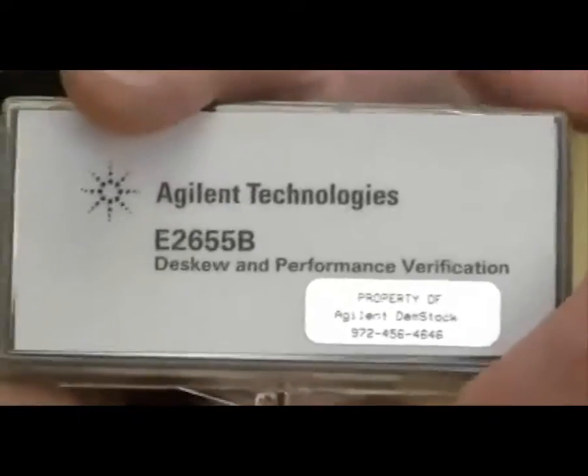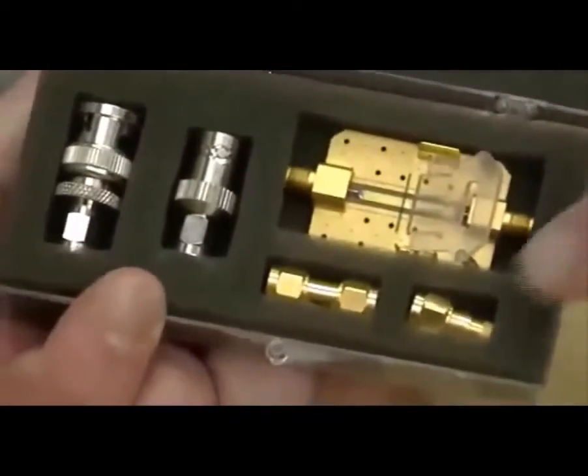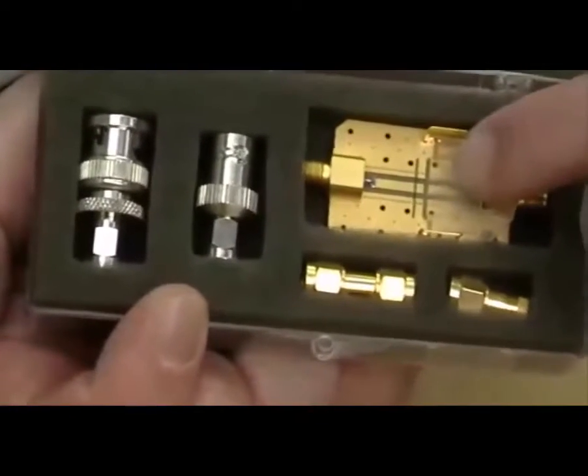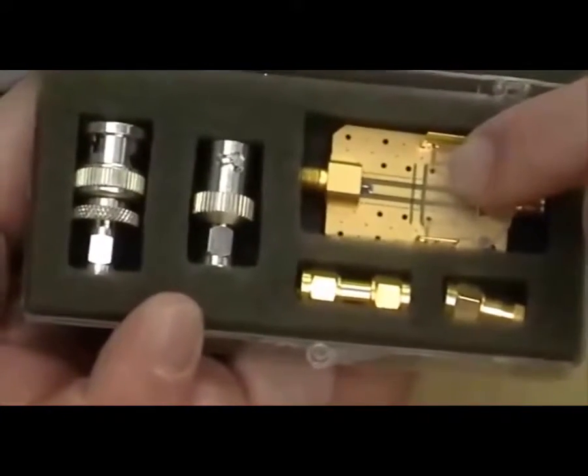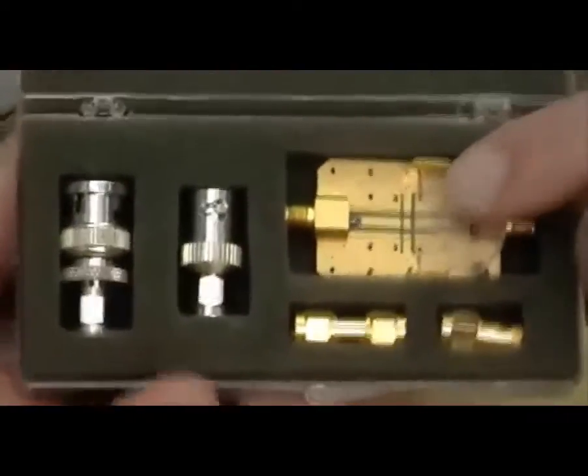This fixture comes with all 90000A series scopes, though not the X series, and it includes some SMA to BNC adapters, a 50 ohm load, and the calibration fixture itself. We'll note that there is a green line on the fixture. This is for doing a channel-to-channel skew calibration with probes.